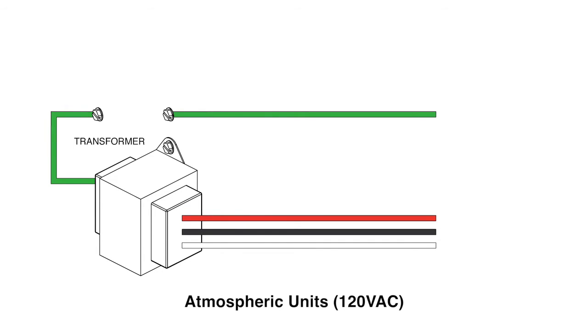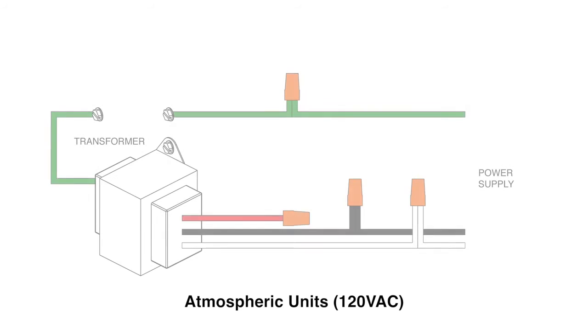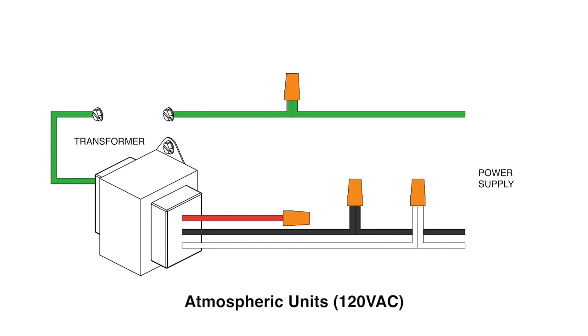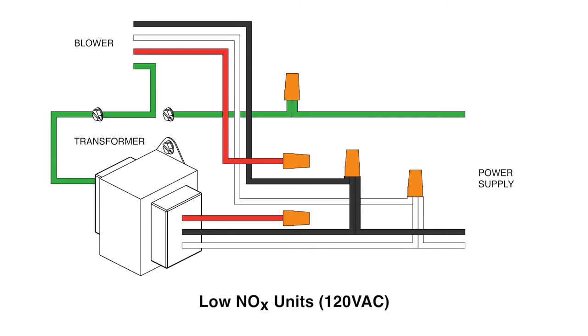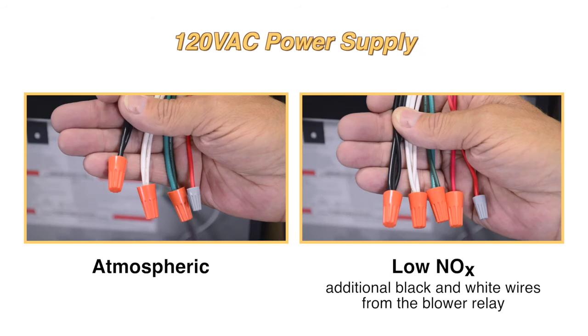For 120 volts, strip back the ends of the incoming wires as well as the black, white, and green wires from the transformer. Attach the incoming hot wire to the black wire from the transformer using a wire nut. Attach the incoming white or neutral wire to the white wire from the transformer. Attach the green ground wires. Use a wire nut to terminate the red wire. For Low NOx models, add each black, white, and green wire from the blower relay to their respective color wires.